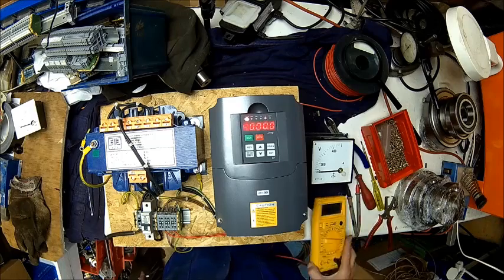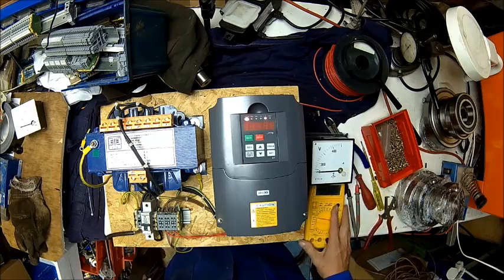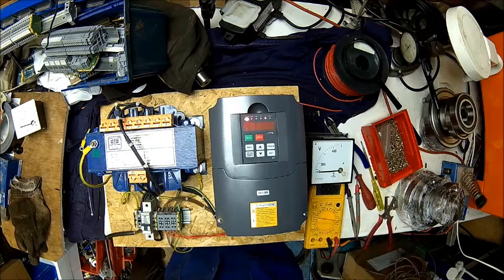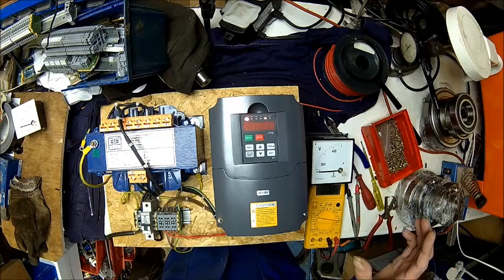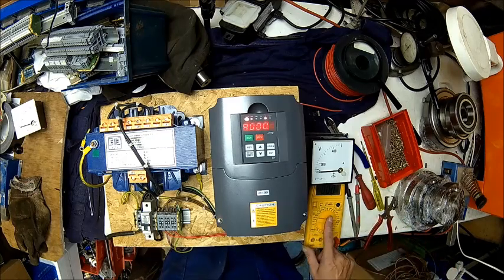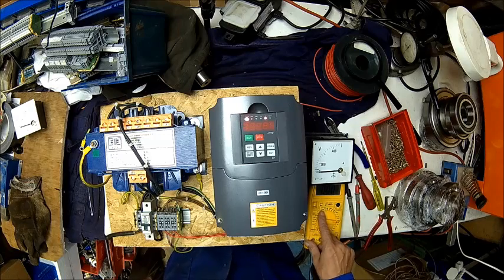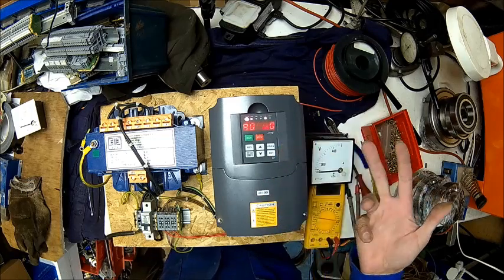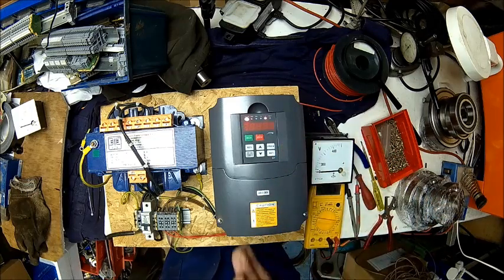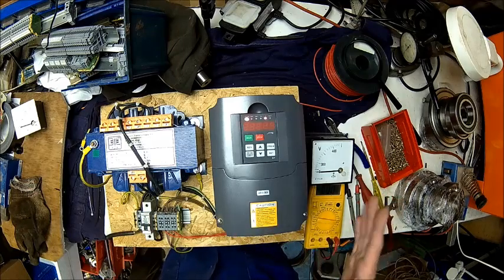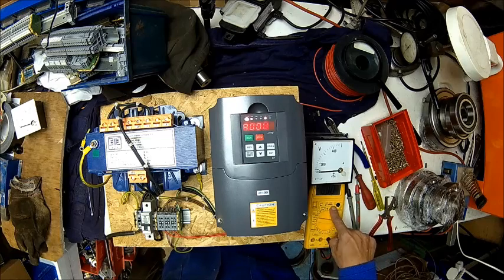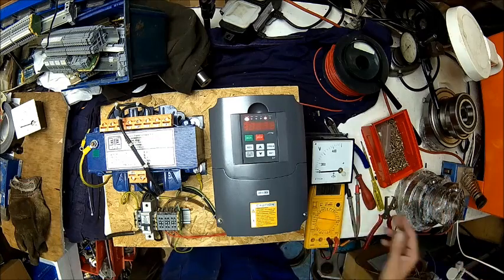And that's the reason why you should never trust a digital multimeter. No matter if it's a rather cheap one, not the cheapest, nor the expensive one I had before, they all do the same. The reason why they're reading too much is the internal resistance is too high, and so they're reading peak voltage, and the peak voltage is actually the DC voltage, which is 560, 580 volts, because it's pulse width modulation. It just cuts this 560 volts into bits, and because these meters are not consuming a lot of power, all you get is an average, which is the 560 volts.